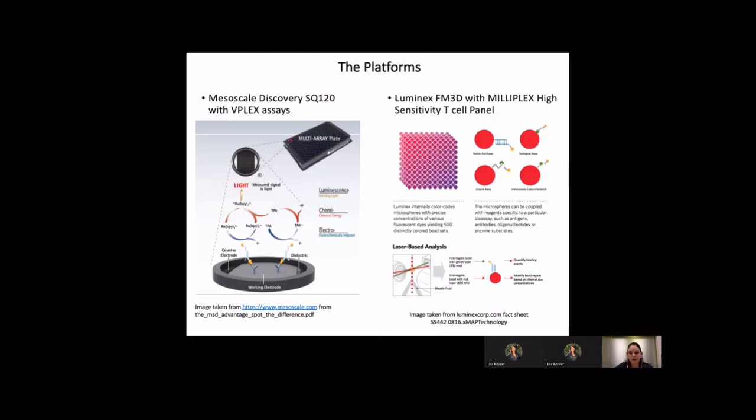A red laser is used to excite the bead, and a green laser excites the PE label. The signal is then sorted for each bead color, and a mean fluorescent intensity of 50 beads per analyte is compared using a single standard curve. FlexMap 3D is a modified flow cytometer that requires routine calibration and performance verification. It operates a fluidic system that requires sheath fluid and occasionally requires a clog removal. The Luminex system also provides high sensitivity and wide dynamic range.